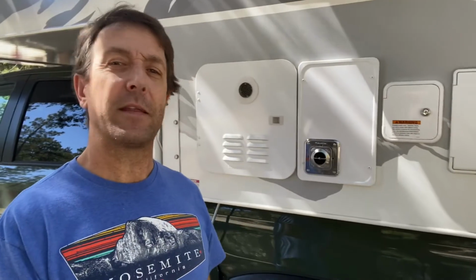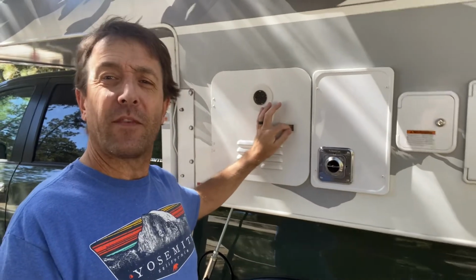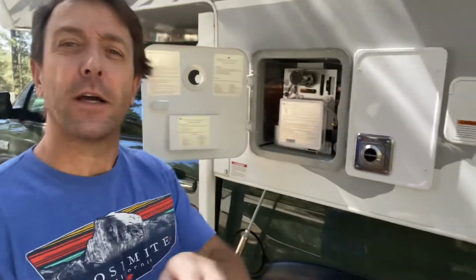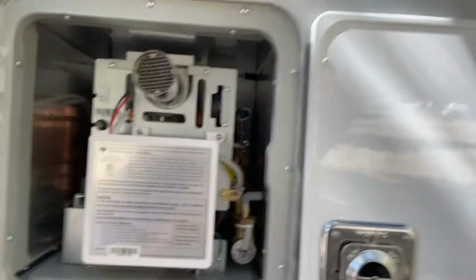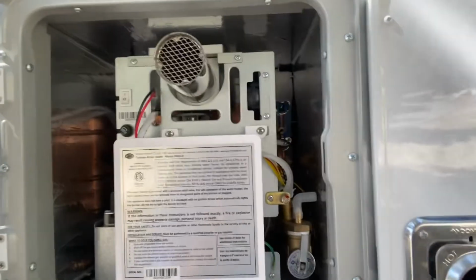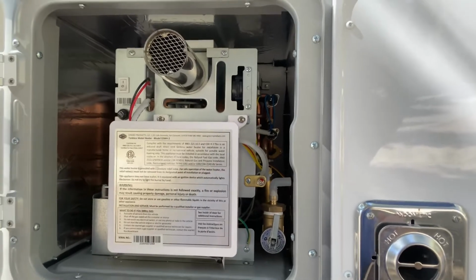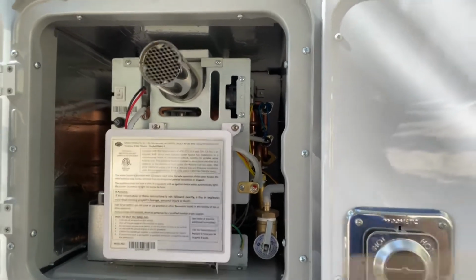The second method, which was the one recommended by the manufacturer when I finally got a hold of someone, is this. This is the water heater from the back side. If you can see in here, it's super crowded. I really did not want to do anything in here. However, they said to diagnose the E03 problem, which is with the ECO sensor.